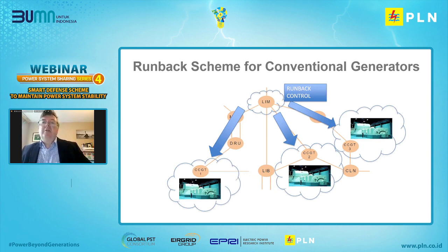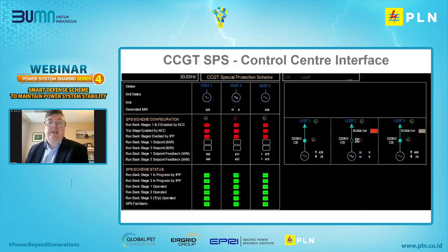So our conventional run back scheme. In this scheme, we have 3 combined cycle plants that are involved, and we've got frequency monitoring at a central location. So we can send commands to each of the 3 stations to reduce power, or if we need to get rid of it quickly, we can trip selected generators off the system. Next slide, please.